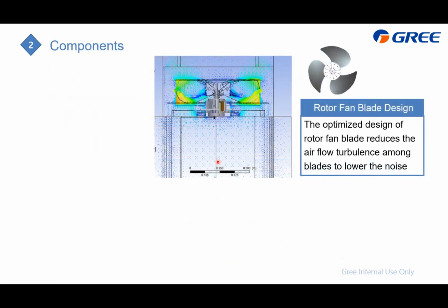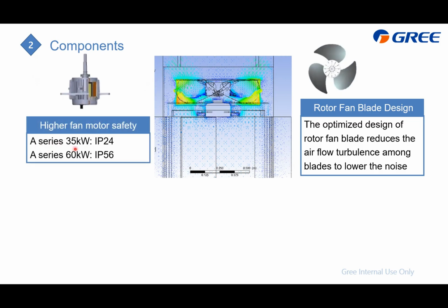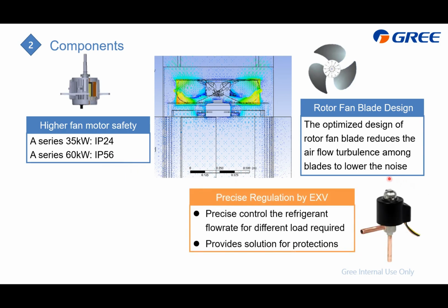For the other components, firstly the fan and the fan motor. For the fan blade, just like what I introduced, we adopt the larger size design, which can increase the ventilation amount. As for the fan motor, for the A series 35 kW is IP24. For the 60 kW is IP56. And inside we apply this electronic expansion valve for the metering device. It can precisely control the refrigerant flow for different loads, and also it can provide the solutions for the protection, which is for the compressor high temperature.